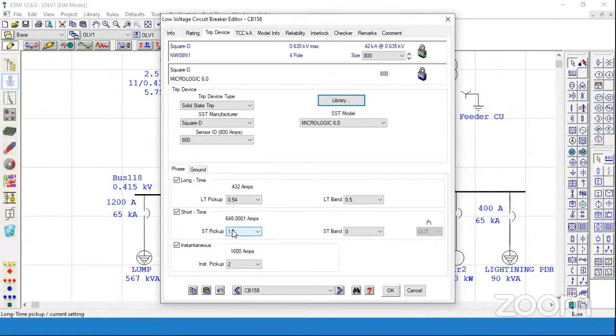Now let's go for 4 times. If current goes to 4 times the load ampere, then we need to isolate this motor to protect it from damage. And for instantaneous we will go to 10 times, as normally the fault current goes to 10 to 12 times. So we will go here for 10 times, and normally for 0.1 seconds.